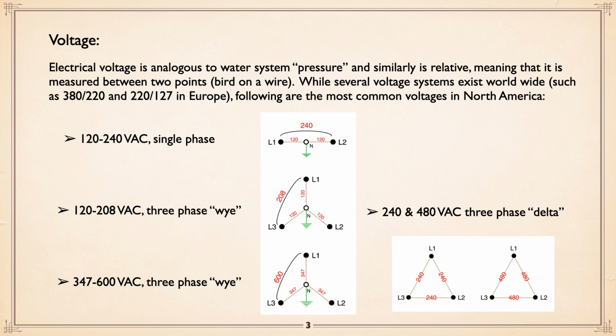Now, 600 volt AC is really nice for powering pumps and whatever of any size. The 347, you say, what use is that? Well, believe it or not, a lot of stadiums actually use that for lighting and whatever. You can get 347 lighting systems. Okay? And last but not least, 240 and 480 volt three-phase delta systems, where you basically have three wires only, no neutral, and between any of them is 240 volt, and put together you of course have 240 volt AC. Same thing in 480 volt. There are reasons, pluses and minuses, mostly minuses, for going with those systems.